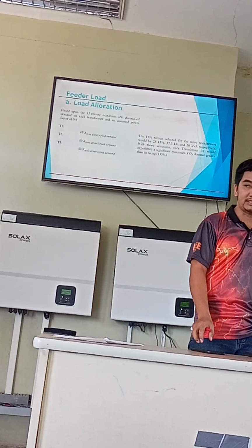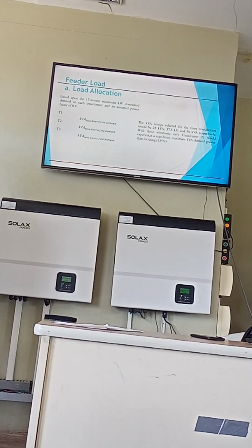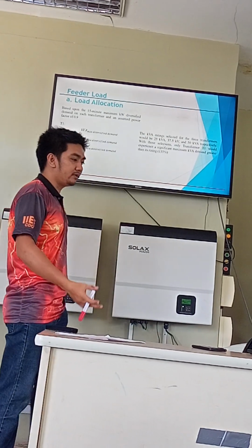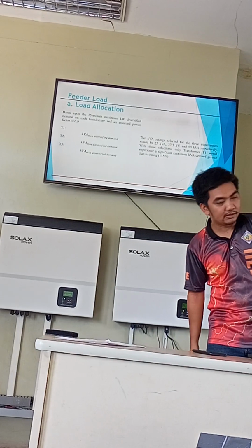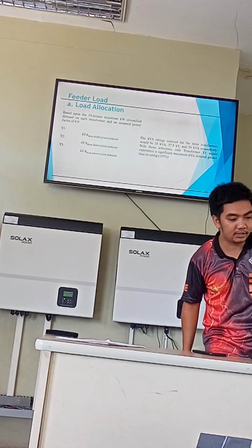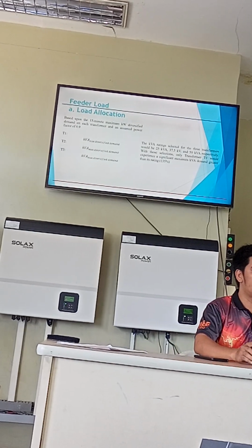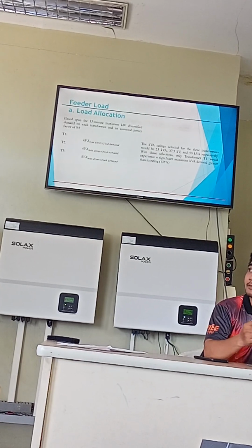If it is just an overestimate, that's fine. But if it indicates that it sustains a further 5% or 10% in your daily load curve or duration, then that's the time we can propose for replacement.